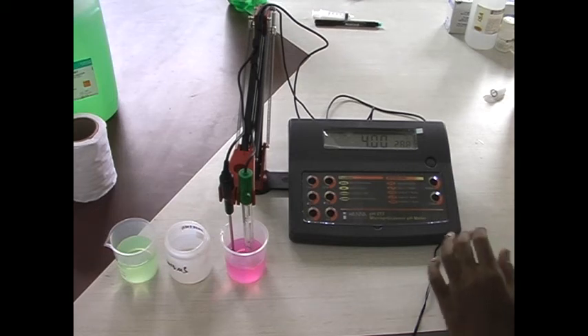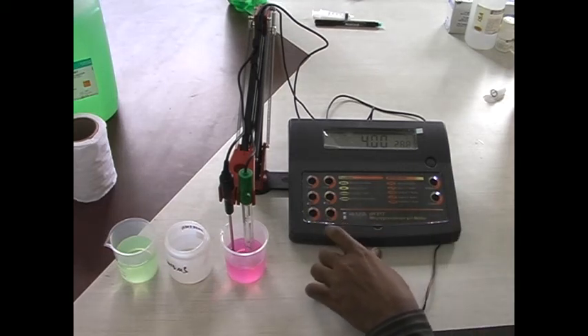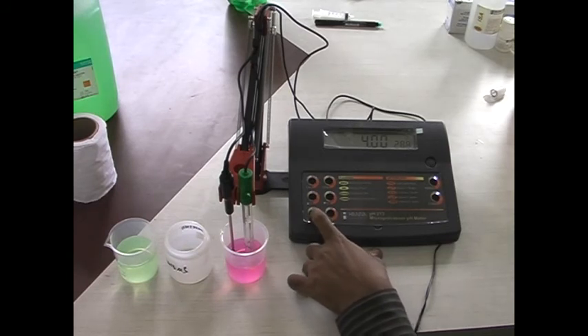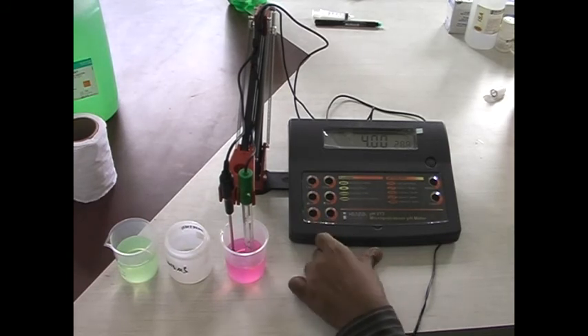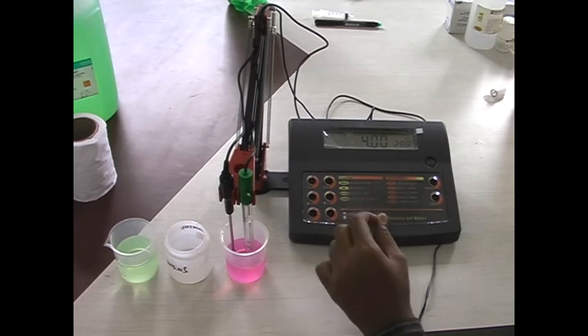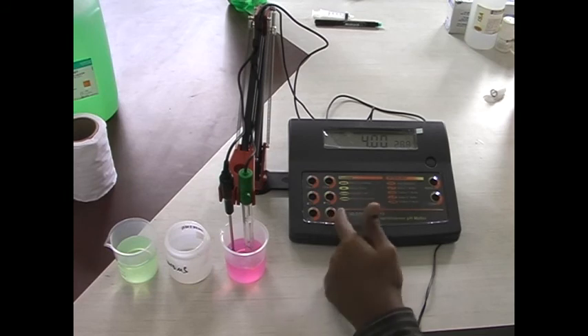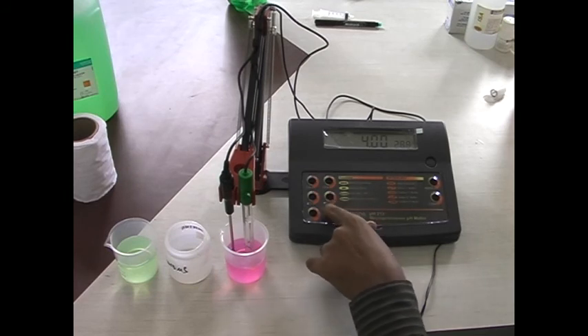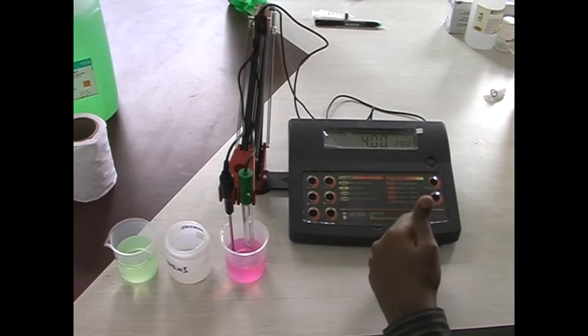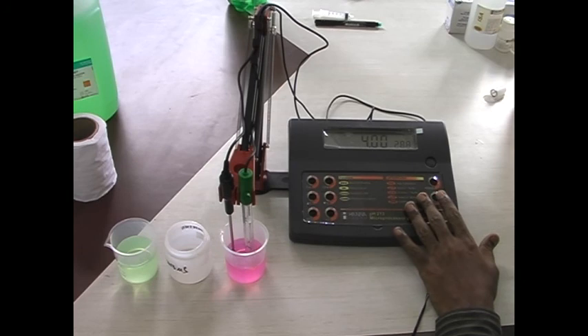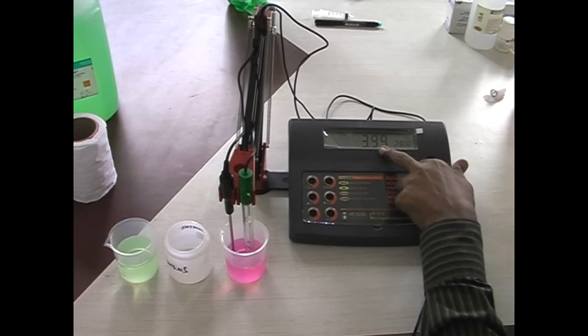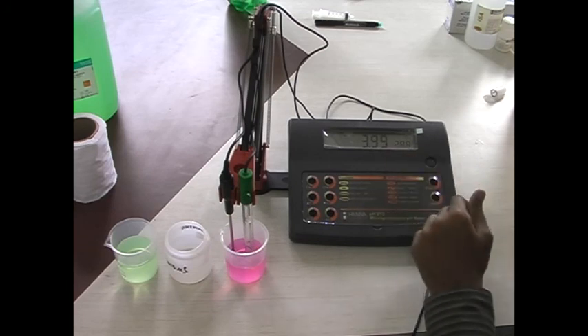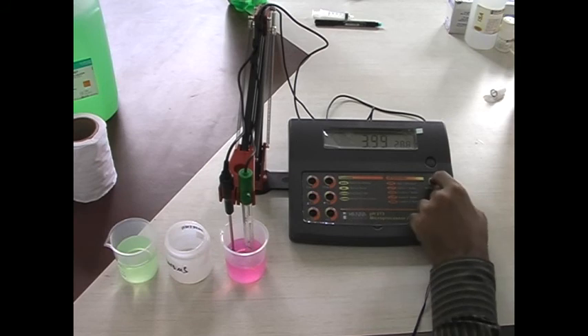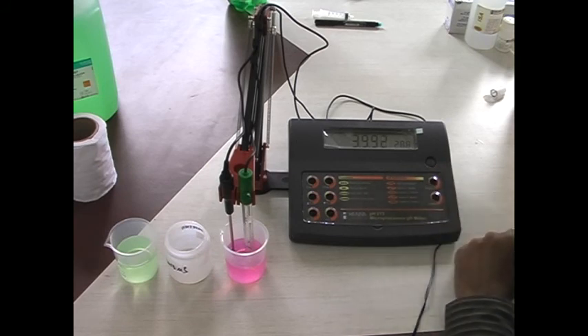Now we will see the function of the MEM key and MR key. The MEM key is used to store the last measurement. It just stores the last measurement, that is 4.01, and when you want to view that last measurement you can just press the MR. It will recall that last stored point. Also it has a unique function that you can change the resolution of the instrument. Currently it is showing 0.01 resolution. You can change to 0.001 just by pressing this range key for better accuracy.